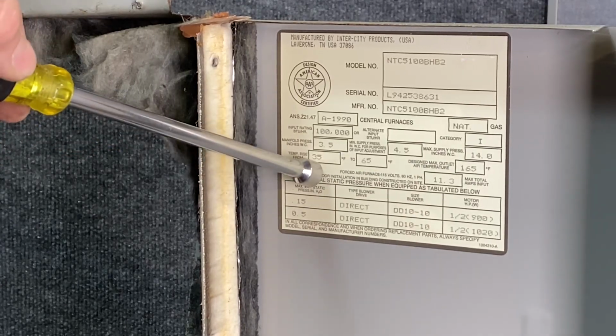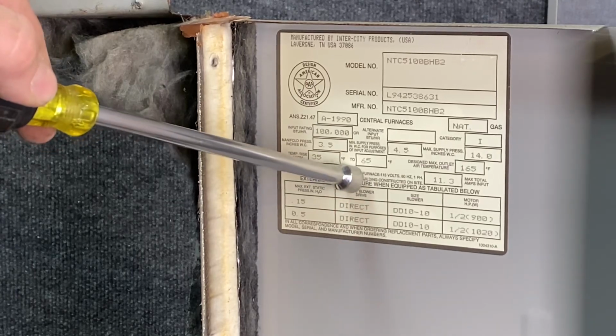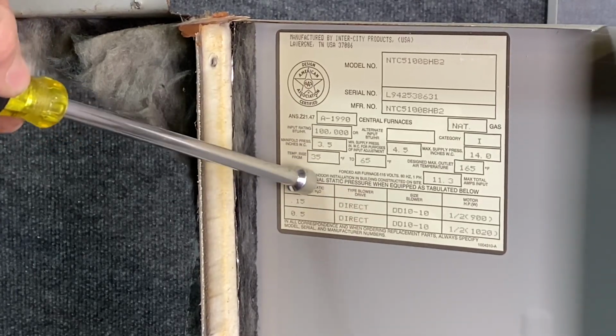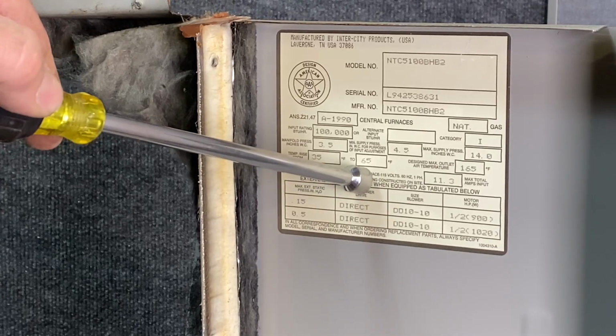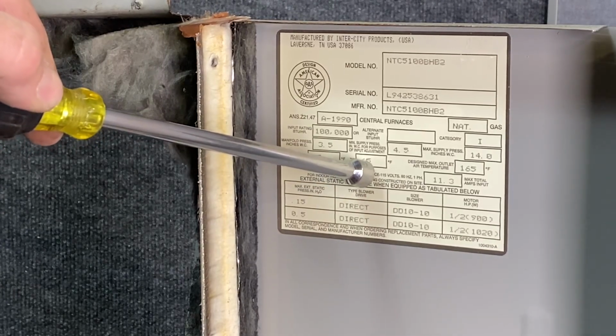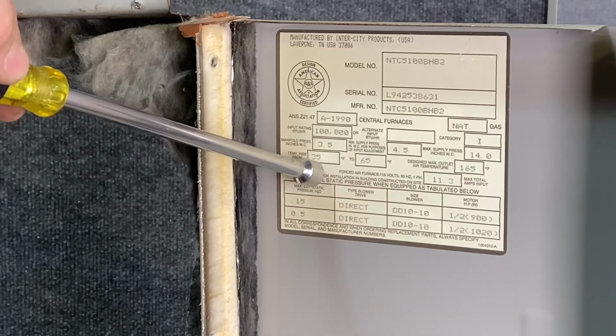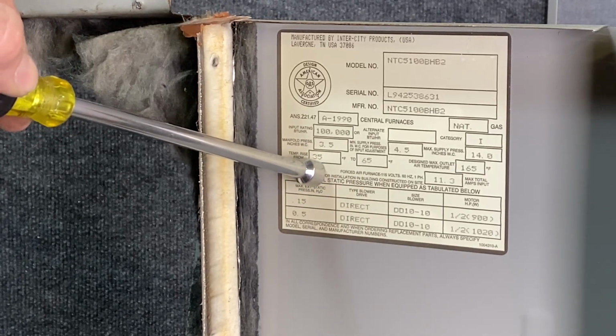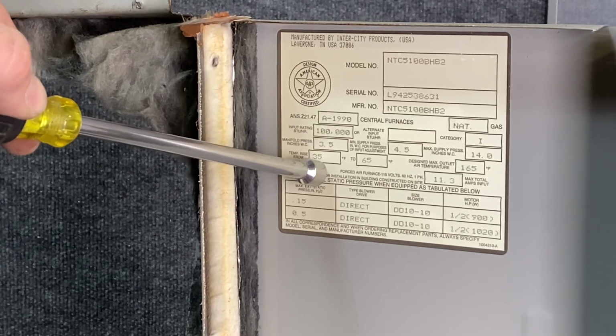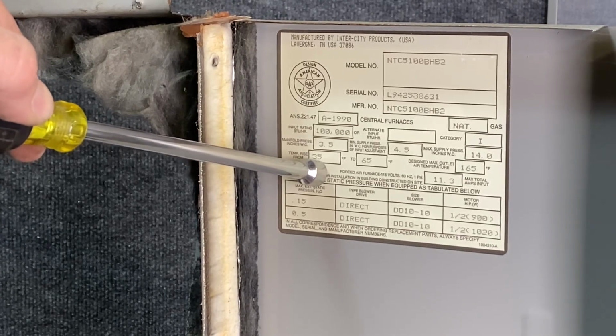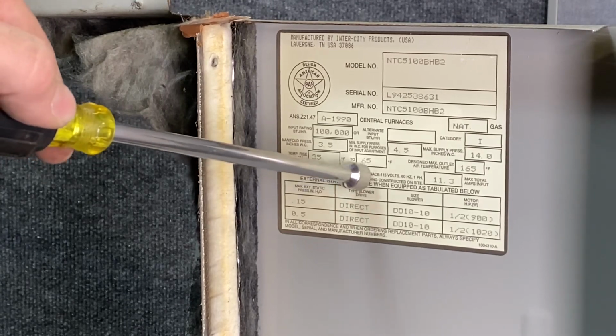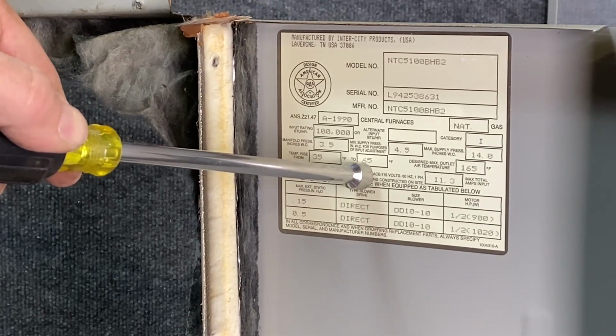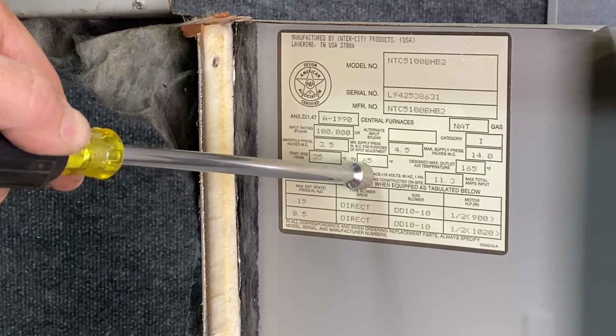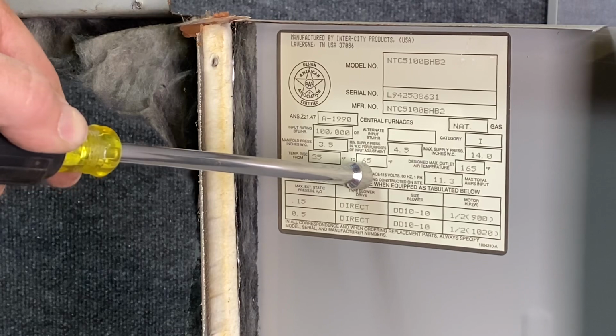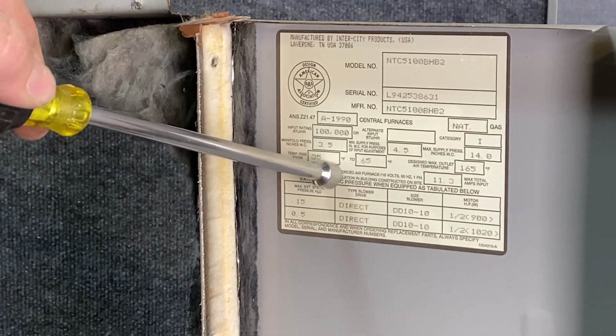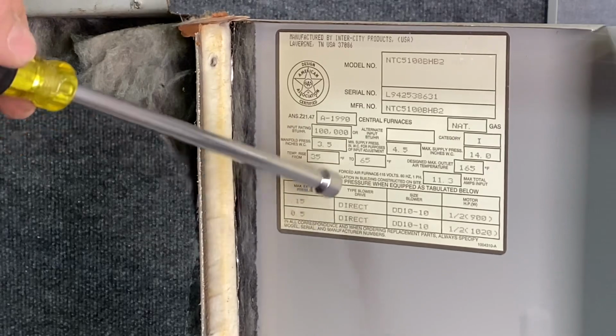Temperature rise, between 35 to 65 degree temperature rise. We're talking about the temperature of the air coming in can be then 35 to 65 degrees lower than the air coming out. It's also called delta T, the difference between air in and the air out. If the temperature rise is lower than 35 degrees difference between the air in and the air out, we're going to have a problem with complete combustion and soot building up in the heat exchanger. If we're higher than a 65 degree temperature rise, we're going to end up with the furnace overheating, and so we're going to have a limit trip. We're going to end up with damaging that heat exchanger. So this gives us a range between the input, between the temperature rise of the furnace.